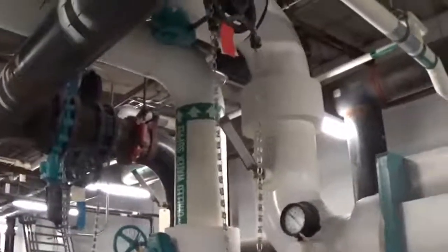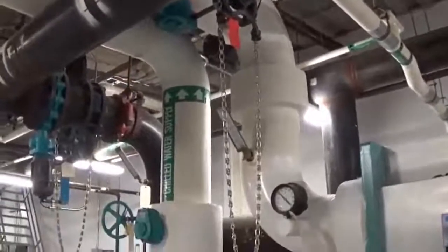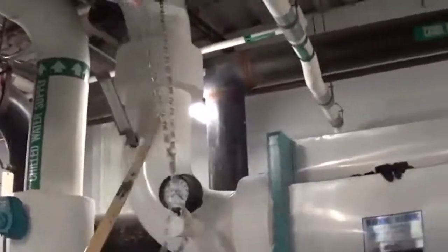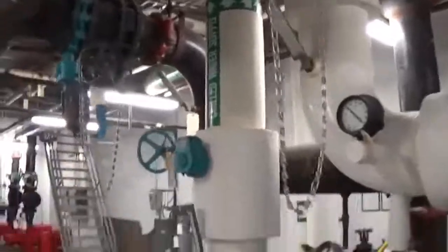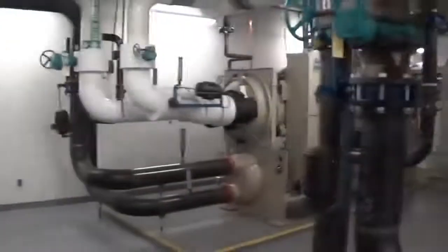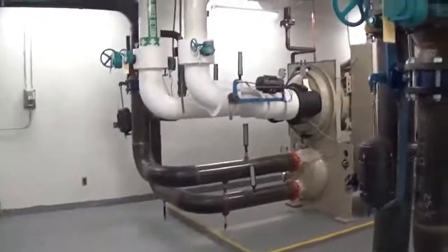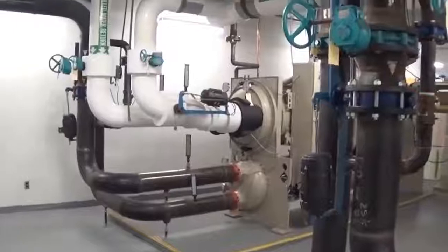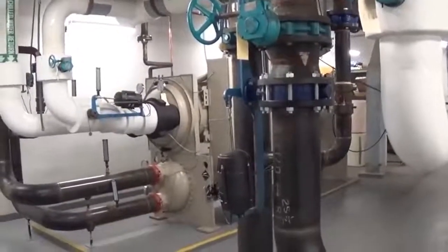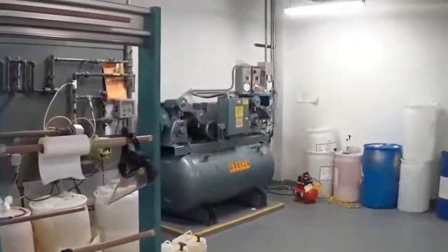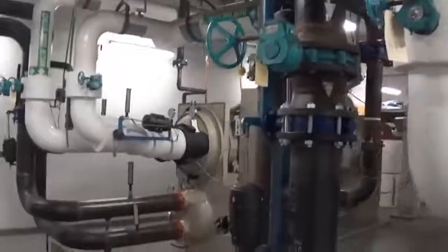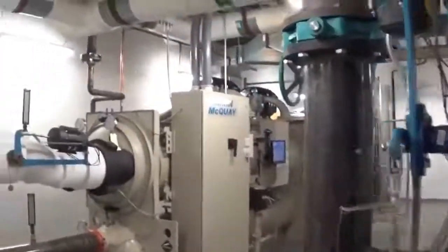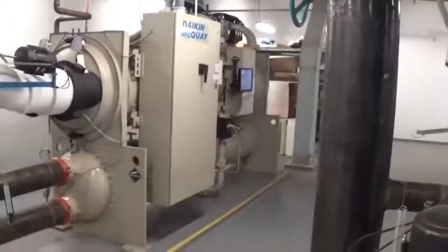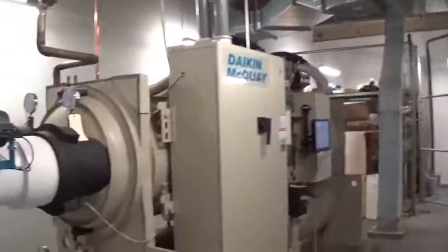So that's a pretty cool operation. There's a series of valves up there. If this water gets too warm, it'll shut these valves off automatically, and then once more just turn your chiller back on to have the mechanical cooling. So pretty cool little system. Like I said, it gets cold here in Virginia, and if we have a good week or two of real cold temperatures, this water will stay cold for a long time, and the owner will reap a lot of benefits here, because this will save him a bundle of electricity in running these machines. Even though these machines are quite economical, you can imagine, you know what your electric bills are at home. If you run these machines for a long time, it's going to cost some money.